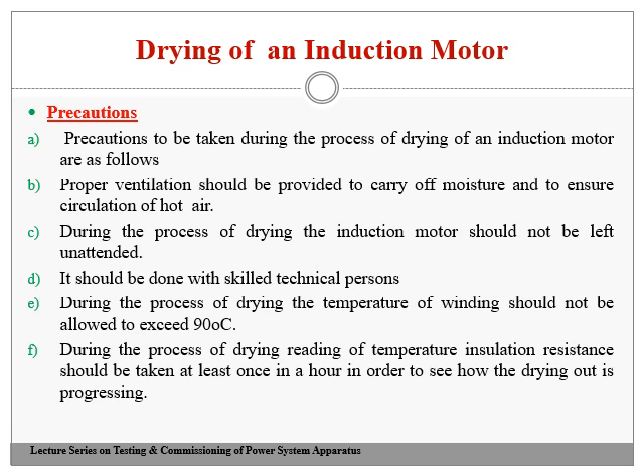During the process of drying, the reading of temperature and insulation resistance should be taken at least once in an hour, in order to see how the drying process is progressing. Depending upon the standards or the manufacturer guidelines, every half an hour or every hour the temperature of the winding should be noted down, or insulation is measured accordingly. It depends upon the frequency of measuring set by the guidelines, or upon the amount of moisture content observed.